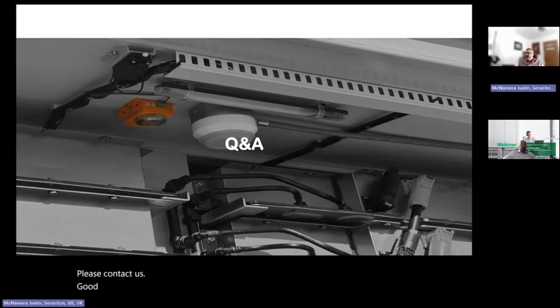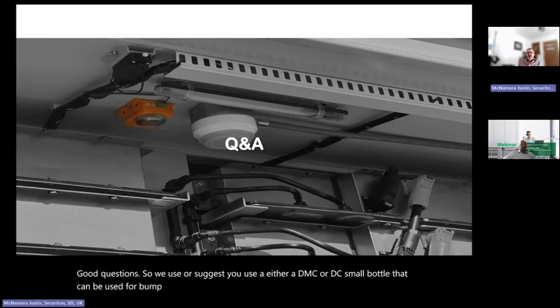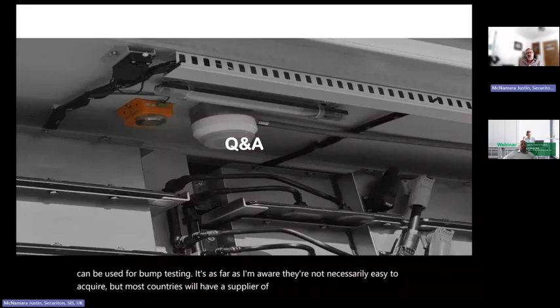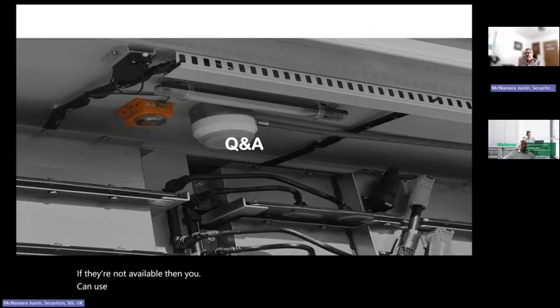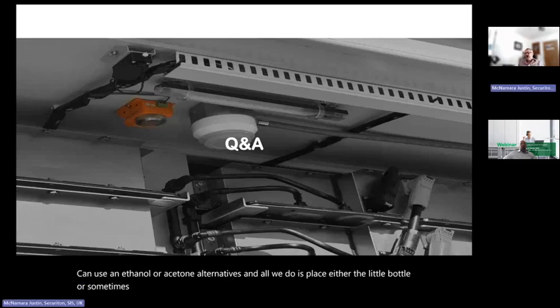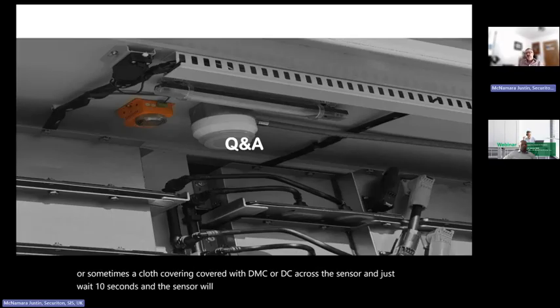Good question. So we use or suggest you use either a DMC or DEC small bottle that can be used for bump testing. As far as I'm aware, they're not necessarily easy to acquire, but most countries will have a supplier of little test bottles containing DEC gas. If they're not available, then you can use ethanol or acetone as alternatives. And all we do is place either the little bottle or sometimes a cloth covered with DMC or DEC across the sensor and just wait 10 seconds and the sensor will operate. Again, we have information that we can share and help you to provide that service.